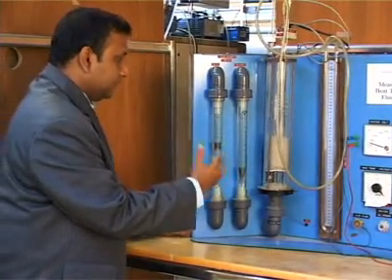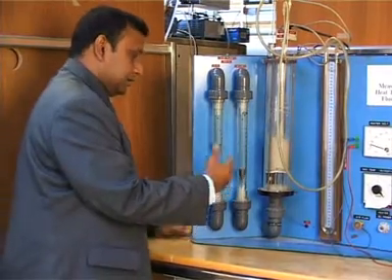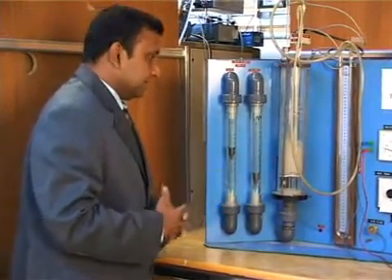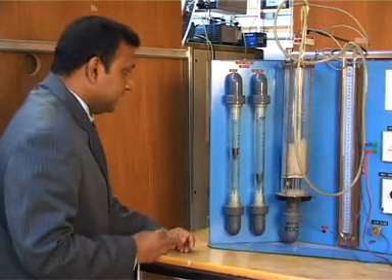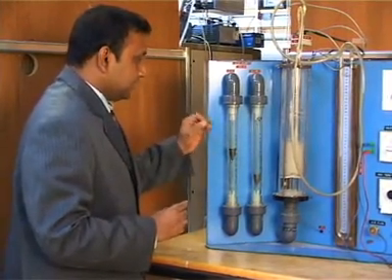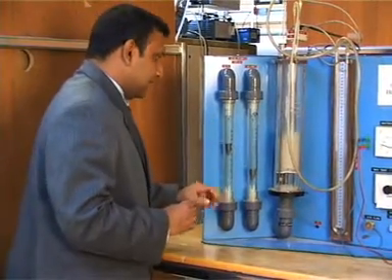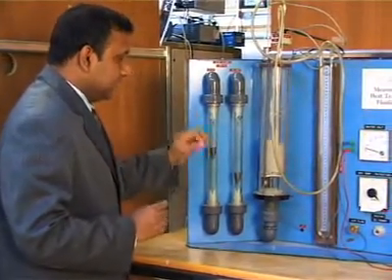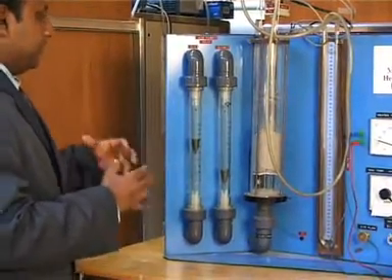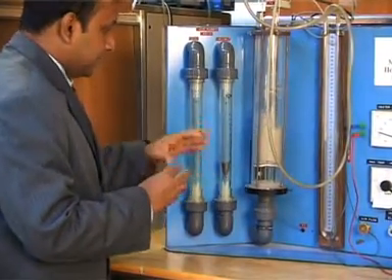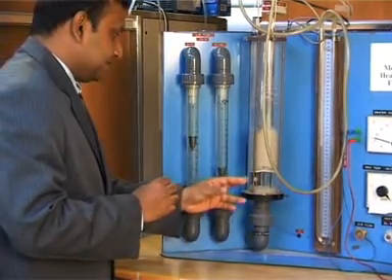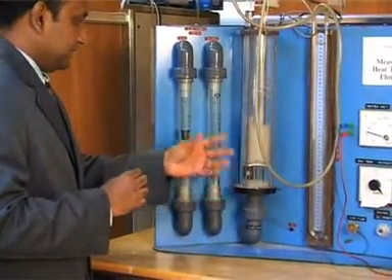So for the startup we use oil burners to heat up the bed to a certain temperature, like 900 centigrade, and then we start injecting our fuel, the solid fuel which we are supposed to burn in the process. When we are injecting fuel into the fluidization bed, that makes a uniform distribution inside the bed, and it also oxidizes at the temperature, and it is also having air from the fluidization process.